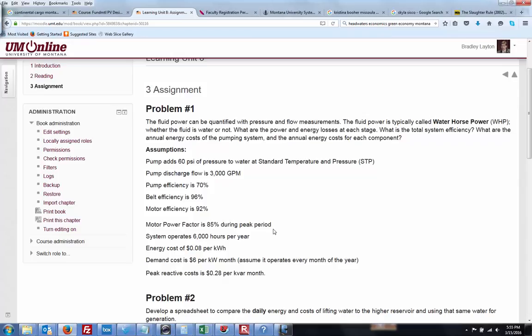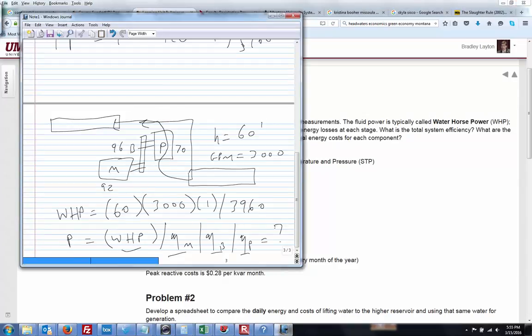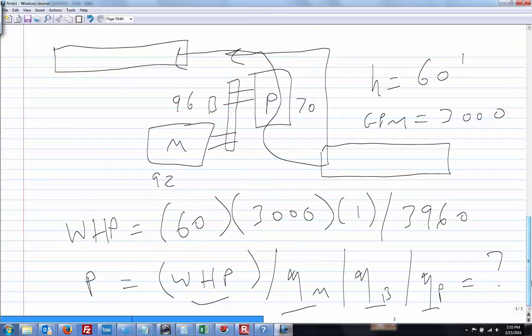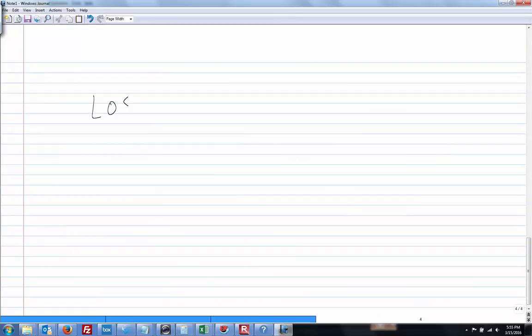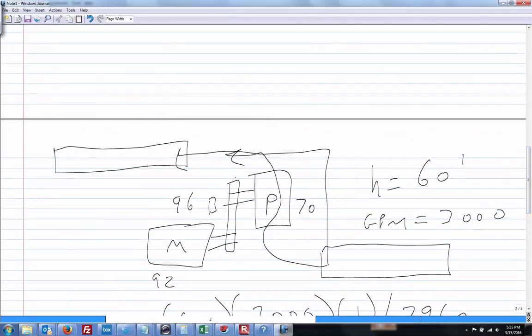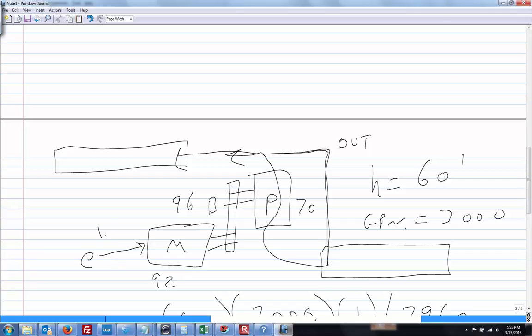It's going to be power in watts. So to get the loss, loss equals power minus water horsepower. So you can basically think of the flow of the water uphill as more or less your output. So that's what you want to achieve. And then the electricity going into the motor is your input.